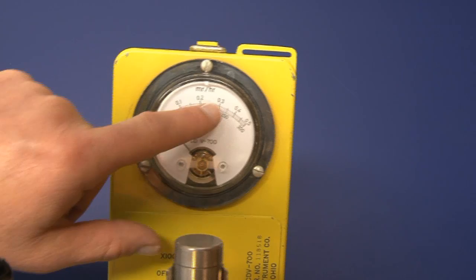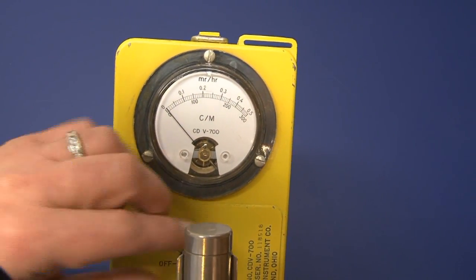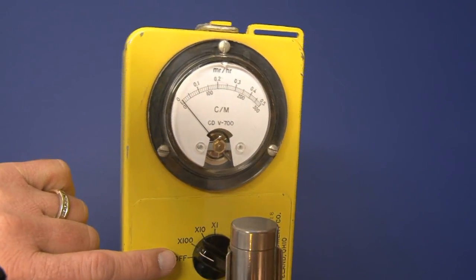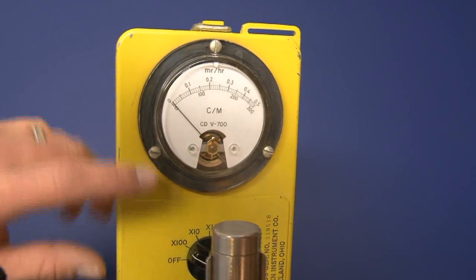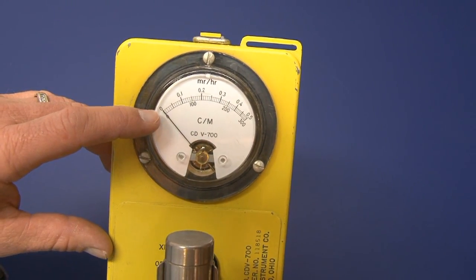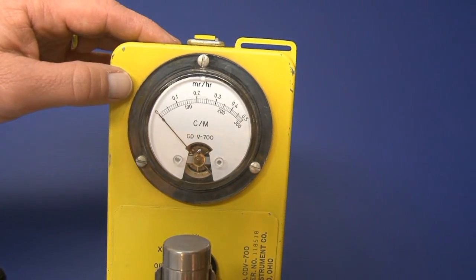You just multiply whatever you're seeing on your meter face times the position on your rotating switch. So on the times 100 scale you've got an operating range of from 0 to 50 MR per hour or 0 to 30,000 counts per minute.